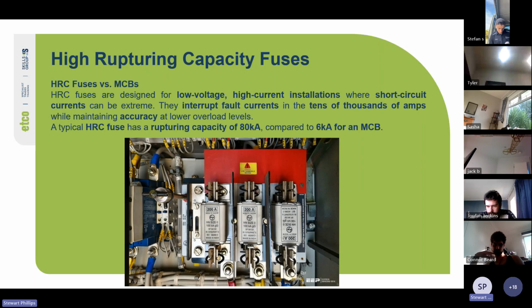That's 80,000 amps. So the fuse in the photo there is rated at 100 kA, so 100,000 amps for its rupturing capacity, and it's a 200 amp, 415 volt fuse.